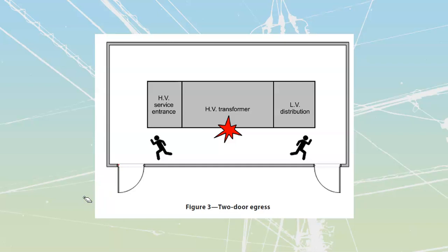Ventilation. Anytime that we have an increase in temperature, there's always a chance that we are going to have failure of our electrical equipment. Remember that for every 10 degrees over 30, we're going to see approximately a 50 percent less lifespan out of any sort of wound component. That's going to be transformers or motors, which are both considered to be wound. We want to avoid having a short lifespan, so we need to ventilate.